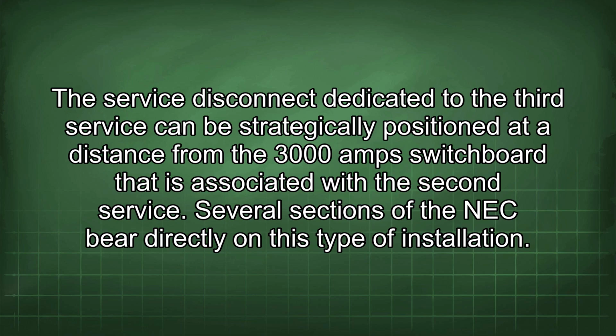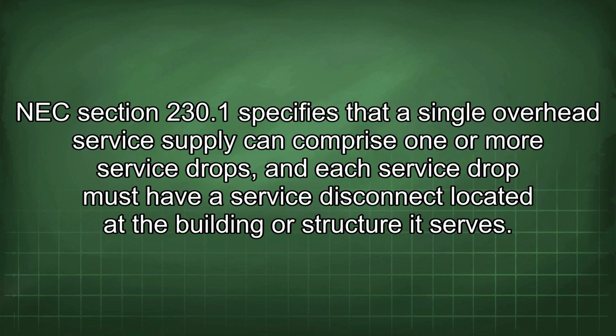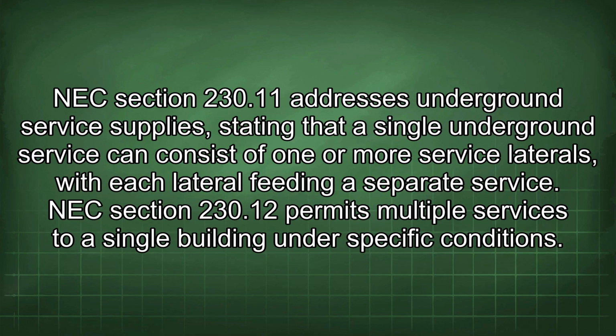Several sections of the NEC bear directly on this type of installation. NEC Section 230.1 specifies that a single overhead service supply can comprise one or more service drops, and each service drop must have a service disconnect located at the building or structure it serves. NEC Section 230.11 addresses underground service supplies, stating that a single underground service can consist of one or more service laterals, with each lateral feeding a separate service.